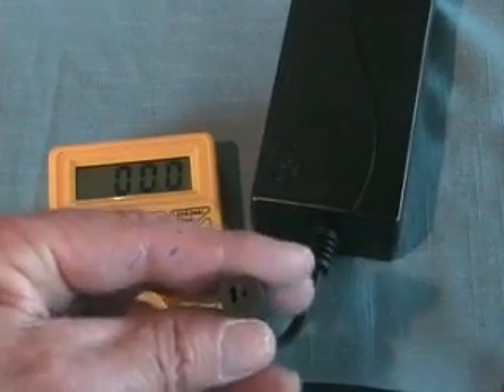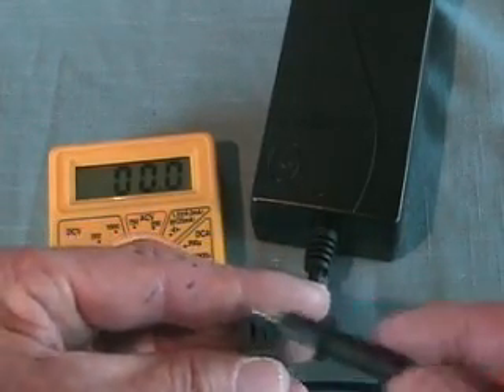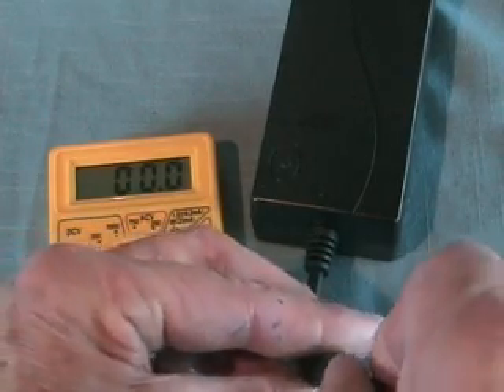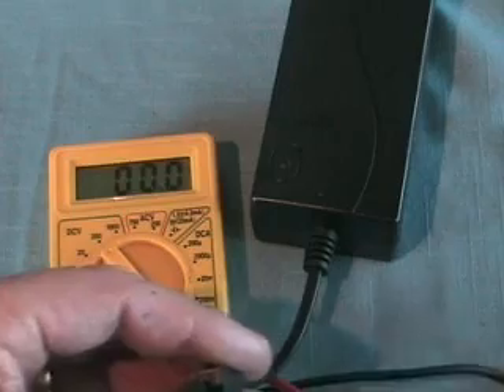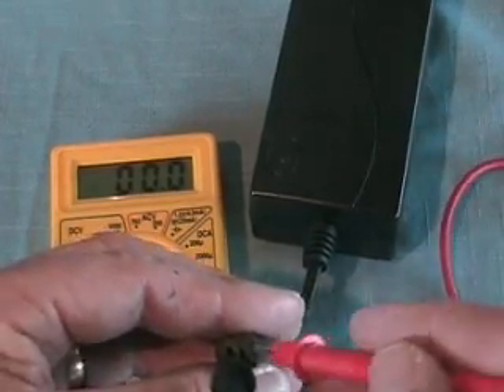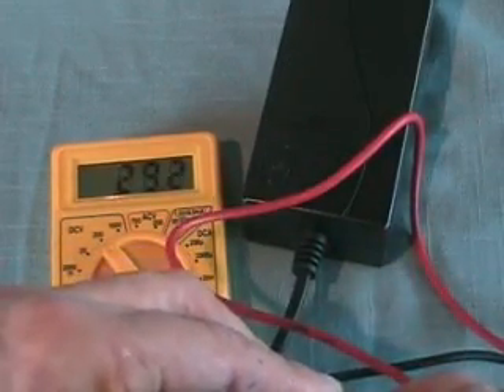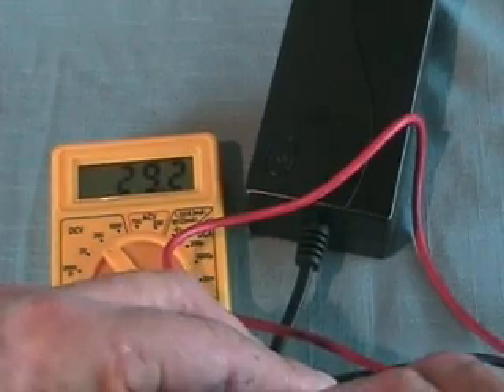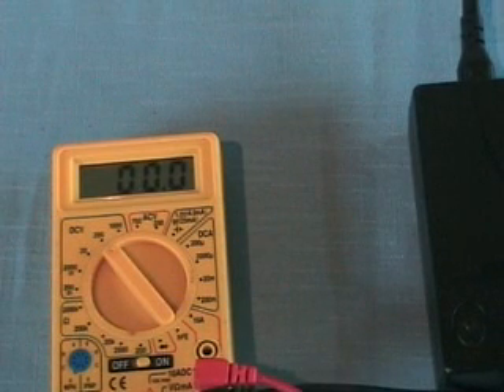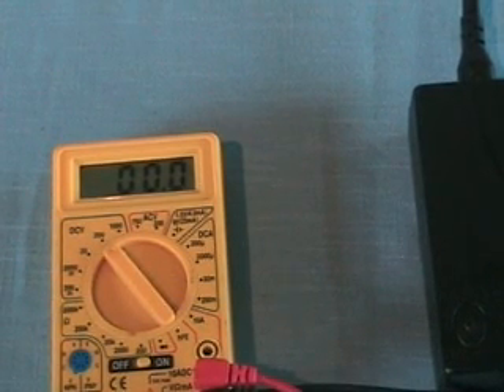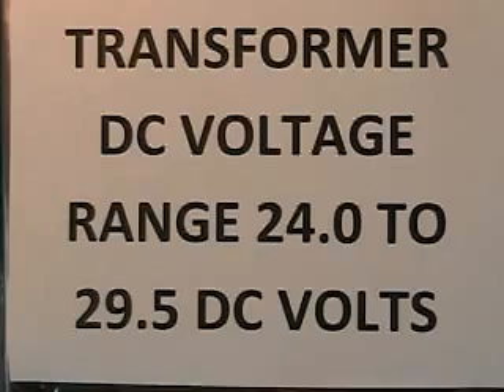On the end of the transformer, you will notice that there are two spade openings. The big one is the negative or black lead. You press that in there, and once again, you should make sure that the ends of your leads are such that they will fit in here, that they're spade connectors. Put the other end into the other side, and as you can see, we go up to 29.2 volts. This is a good transformer. The range of voltage on the transformers is 24 to 29 volts DC.